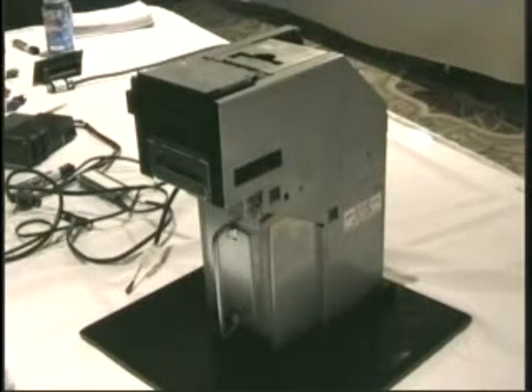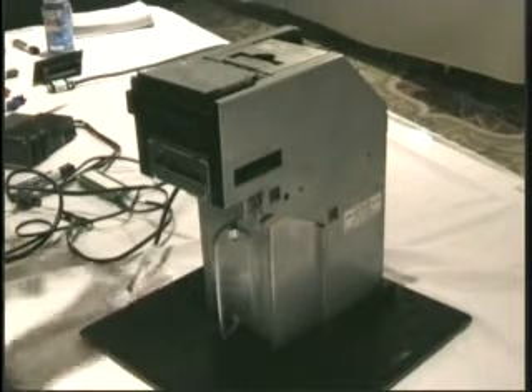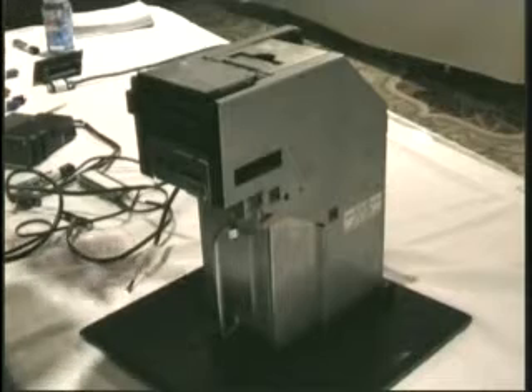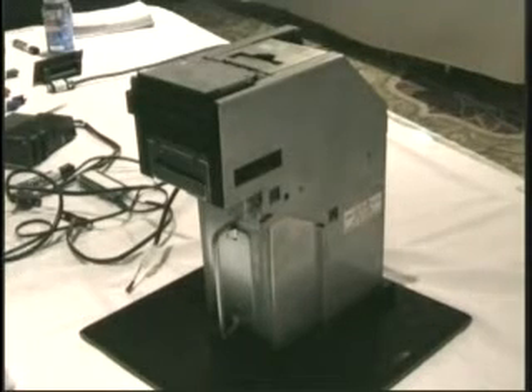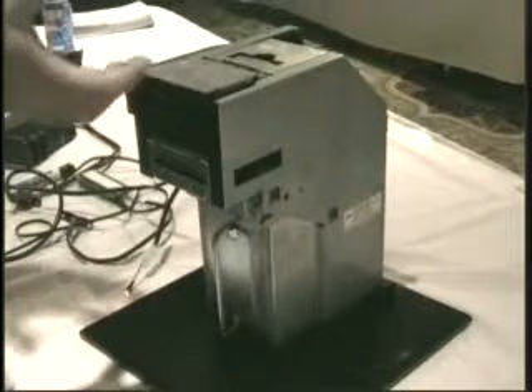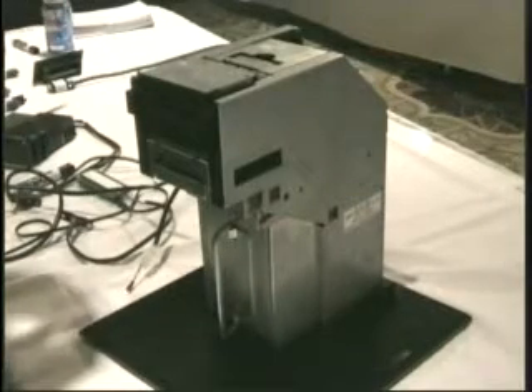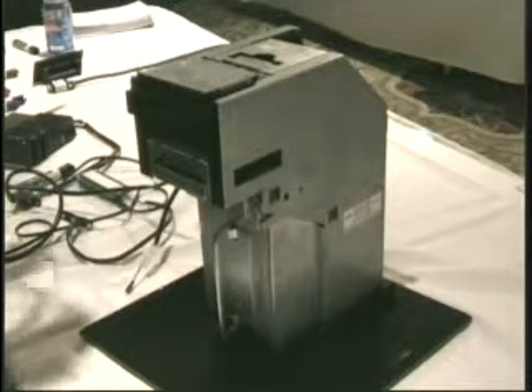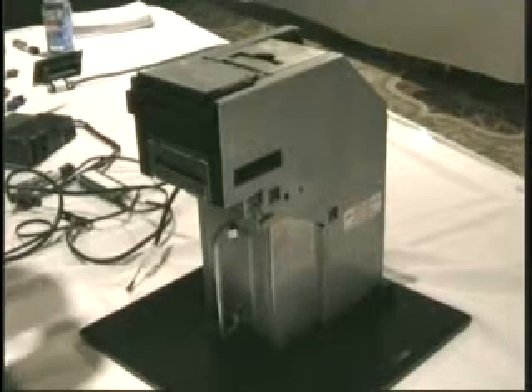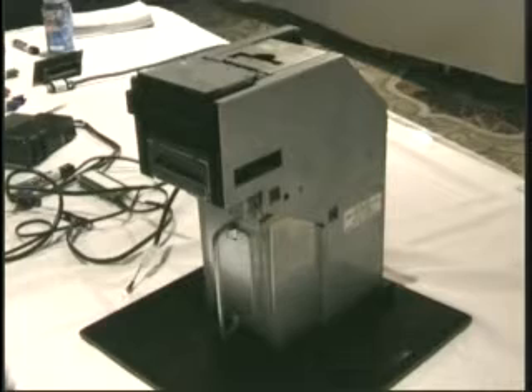Well, but a minute ago it did this. I believe you, but I can't fix what ain't broke. It's working now. Intermittent faults will drive you nuts. If you're not there to see what happens or to hear the noises that it makes, it's pretty hard to start diagnosing it. And a lot of times what you're going to find is broken wires, bent pins on a plug, something that's been pushed out of position, and when the motors in the validator vibrated just right, you lose connection on one pin. Unfortunately, it's when a signal needed to run down that wire. And the validator shuts down. It goes into a fault. Problem is, by the time you get there to take a look at it, it's vibrated back together and it's working now.